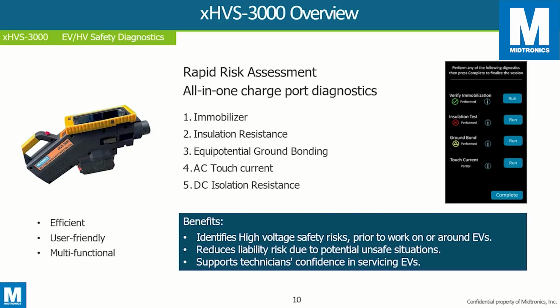AC touch current. So what is AC touch current? It can be a dangerous issue when it arises, which is when there's a ground fault problem with the charging station and the vehicle has some flawed components, because over time things come loose or degrade through vibration and weather. Then the charging station won't be protecting the driver or any bystanders because it has that ground fault, and in that case the vehicle wouldn't either because of these failed components. So the risk here is that there would be AC current flowing on conductive surfaces where it should not, for example door panel, handle, rims, any conductive surface, and someone who just touches it nearby could be electrocuted. The risk here is death, because we're talking AC power.